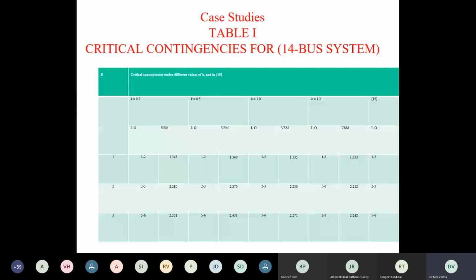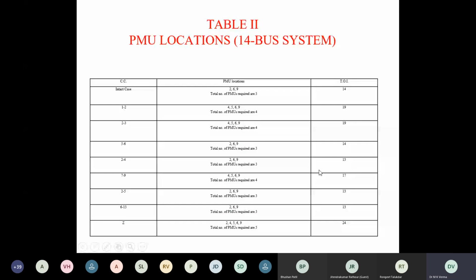So this is the considered PMU placement for the 14 bus system for voltage stability margin. These were the different locations of PMUs. In that case, you obtain 3 locations of PMU: bus number 2, bus number 6, and bus number 9, and the observability index was 14, which is just equal to the number of buses in the system. For different outages, you obtain different observability indexes. For most cases it is more than 14, and for some cases 13, less than 14. These are severe contingencies, severe line outages. Then he combined the PMU locations for all the contingency cases, which resulted in PMUs at 5 buses: bus number 2, 4, 5, 6, and 9.